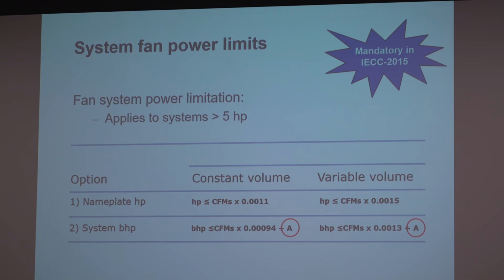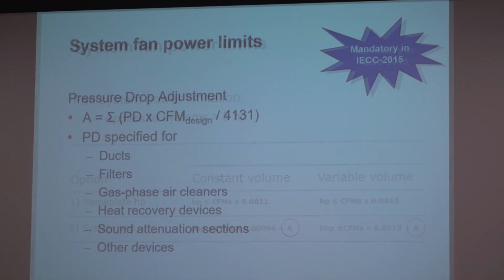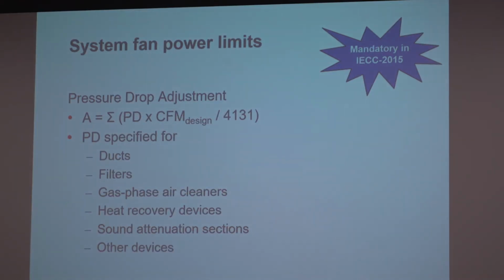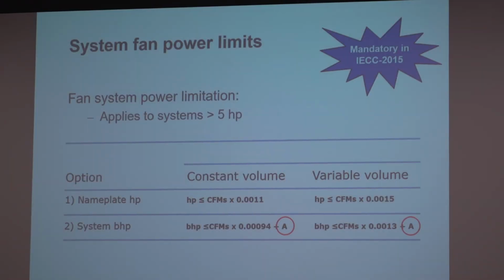Let's see, here's the system fan power limits. It's an equation. I will bring your attention to this little A term. This A term is the adjustment number. It's essentially, and it's on the next slide, a summation of the pressure drop times the CFM divided by the constant there that converts the units. So A is effectively an addition to your brake horsepower limit, and you only get this A term if you're using the brake horsepower path.